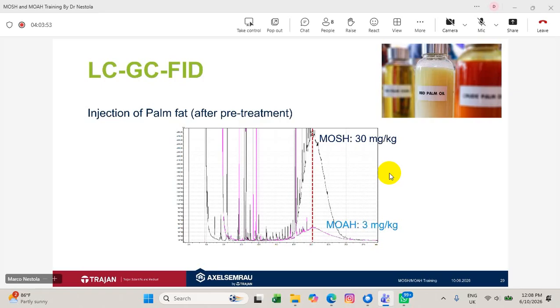And since these are 2 different GC columns we are using that are not connected to each other, typically it can be possible that you have a shift between both channels. That's one of the things we are checking doing FAT, SAT. Also, when the customer uses an instrument, it's a check that is easily done and can be corrected in a quite easy way.